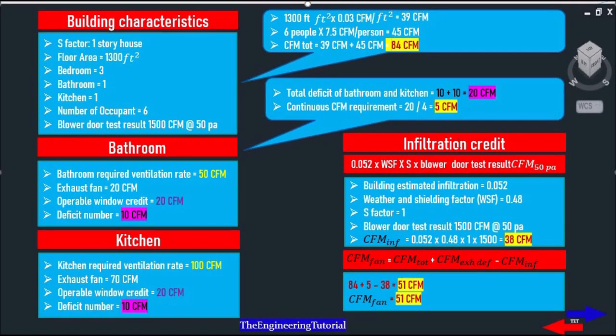And lastly infiltration credit. To calculate the infiltration credit we will use this equation. 0.052 multiply by WSF multiplied by S multiplied by blower door test result. The building estimated infiltration is 0.052. The weather and shielding factor is 0.48 and the S factor is 1. And the blower door test result is 1500 CFM at 50 Pa.